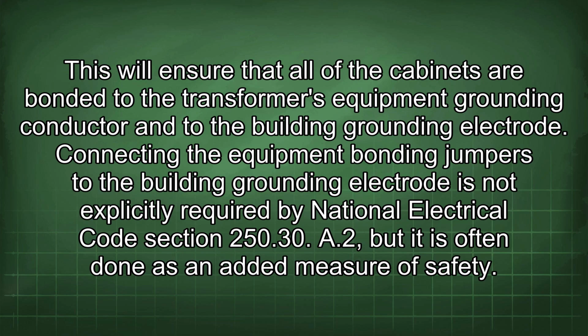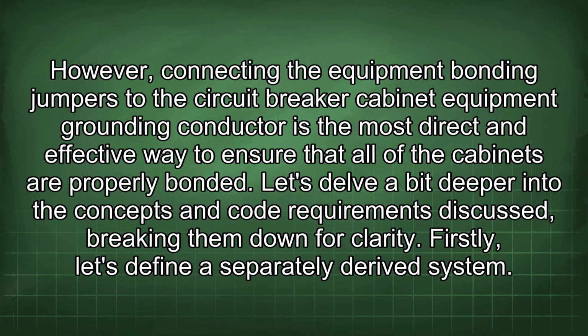Connecting the equipment bonding jumpers to the building grounding electrode is not explicitly required by National Electrical Code Section 250.30(A)(2), but it is often done as an added measure of safety. However, connecting the equipment bonding jumpers to the circuit breaker cabinet equipment grounding conductor is the most direct and effective way to ensure that all of the cabinets are properly bonded.